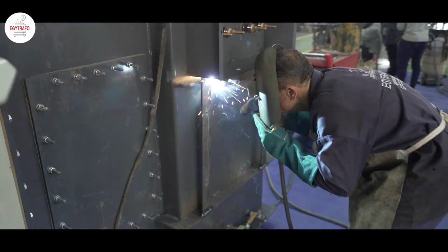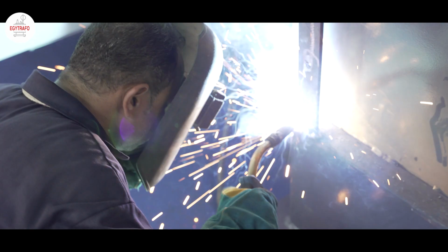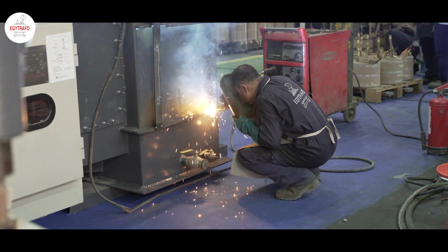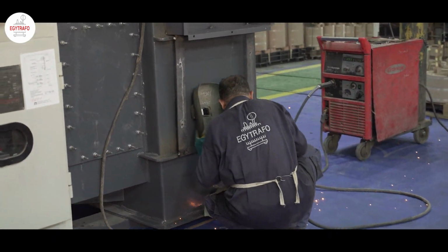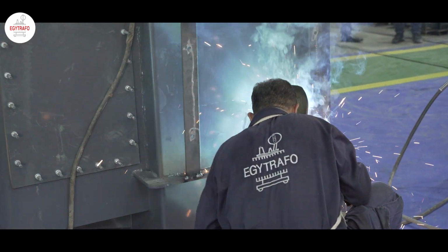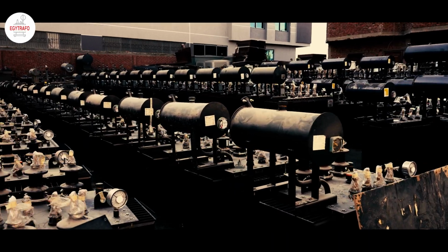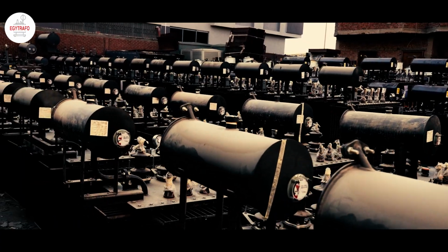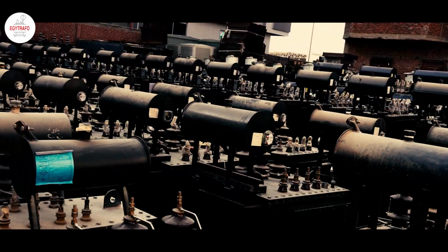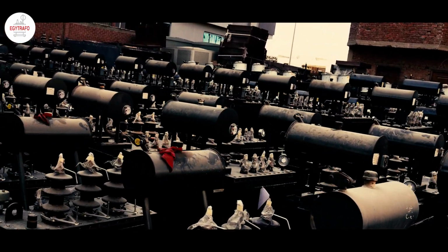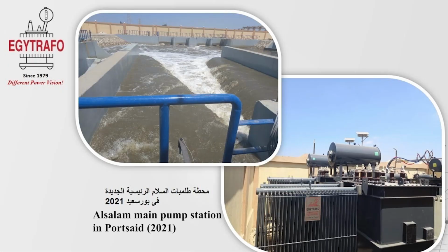All protection device flanges, bushings, tap switch drive, and lifting lugs are fitted on the tank cover. The complete tank is tested and approved according to standards. All metal parts are carefully sandblasted. The initial protective coating is made up of a single coat of 1-pack epoxy paint.